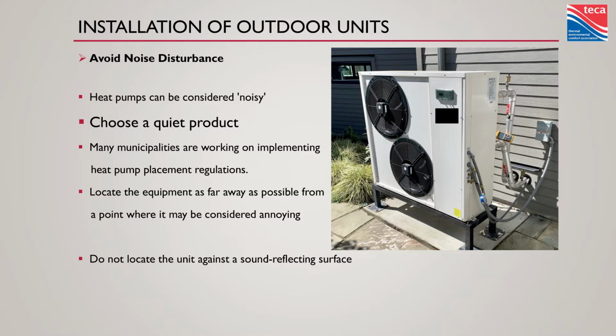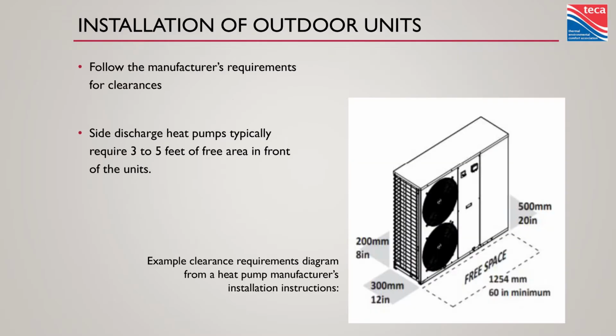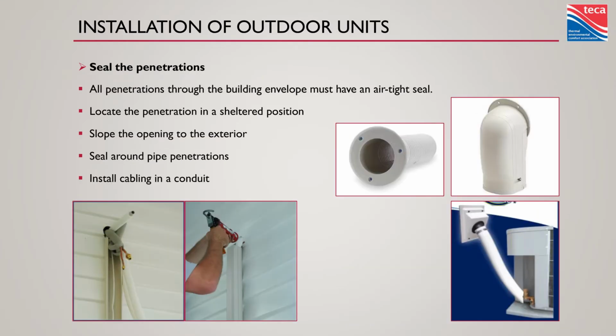So pretty typical to need somewhere around 5, even 6 feet off the front of a side discharge heat pump or off the top of a top discharge heat pump. So top discharge heat pump under a deck, not a great idea. But that could maybe live under a deck, rejecting heat out to the outside or absorbing heat from the outside. Try not to put these things right in front of the front door. I don't know if you like the people that canvass your neighborhood, but if it's a cold day, it's even colder air coming off of that heat pump. It's not a warm greeting to your friends and family.